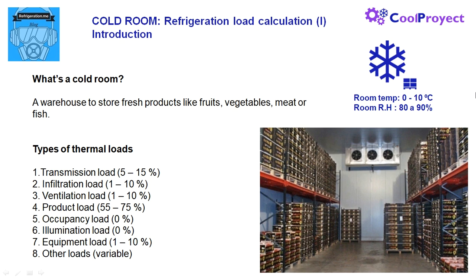Number one, we have the transmission load. That's the load due to heat transfer through the walls, roof, and floor of the room. This load accounts for 5 to 15% of the total load.